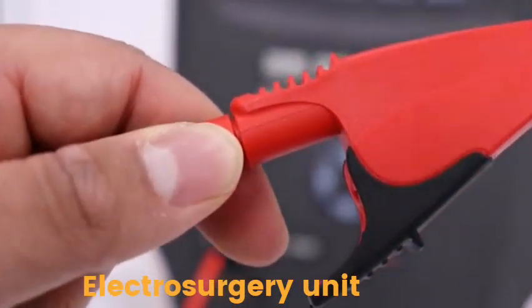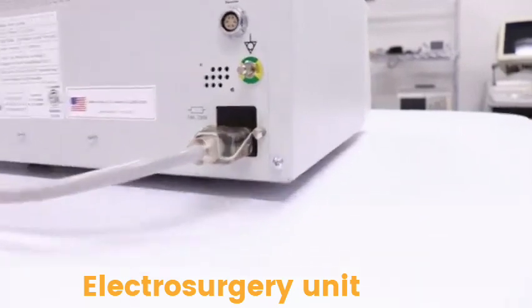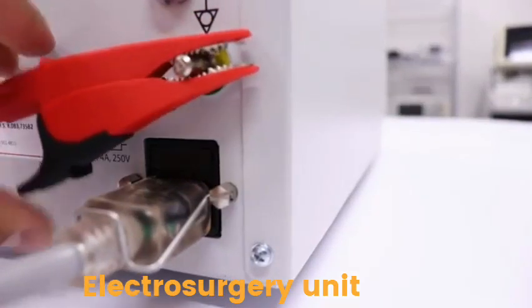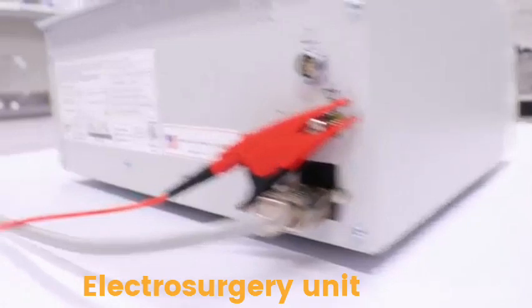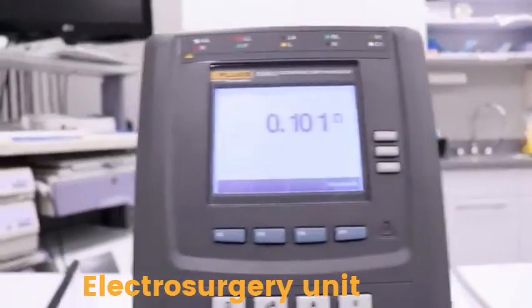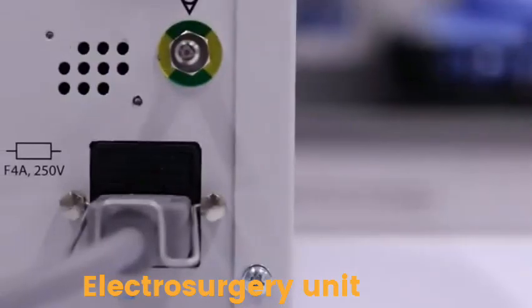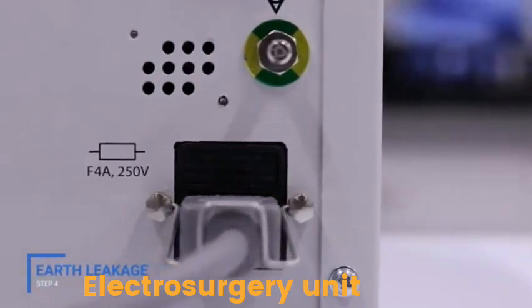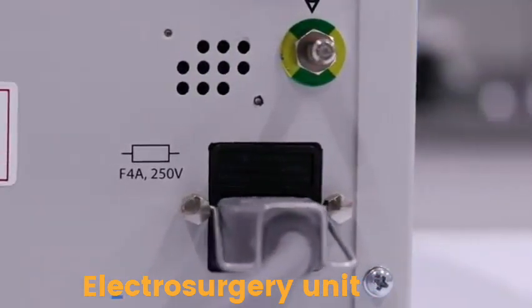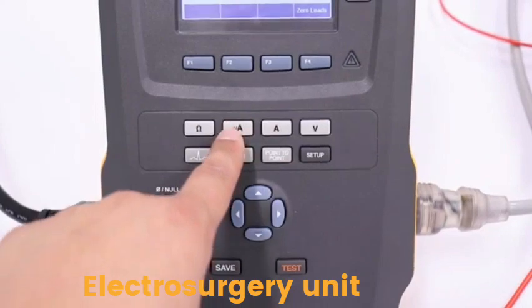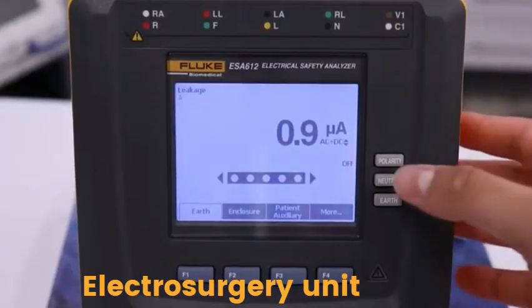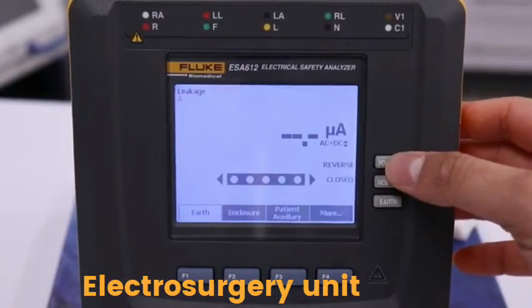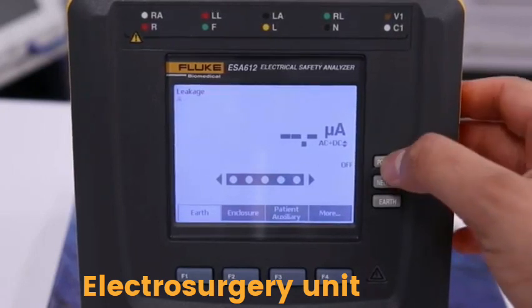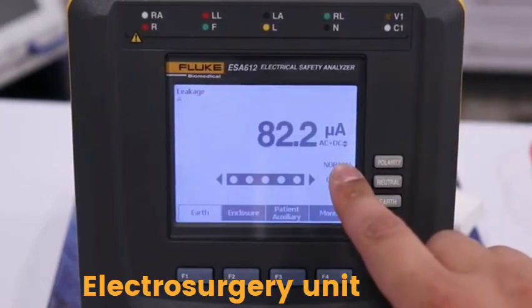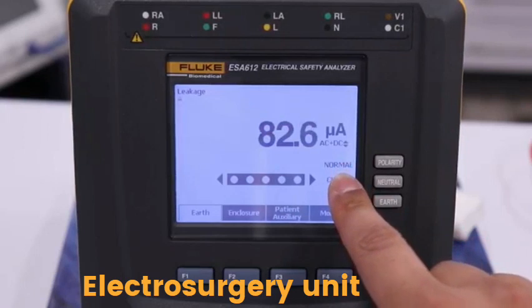Remove the ground end of the test lead from the ESA and connect an alligator clip. Place the alligator clip on the ground lug at the rear of the GI4000. The ESA will measure ground resistance. The earth leakage test measures the current flowing down the protective earth conductor with the mains inlet lead. To measure earth leakage, press the microamp button. Cycle through polarity, neutral, and earth settings by pressing the buttons on the side of the screen. Select normal polarity and closed neutral.